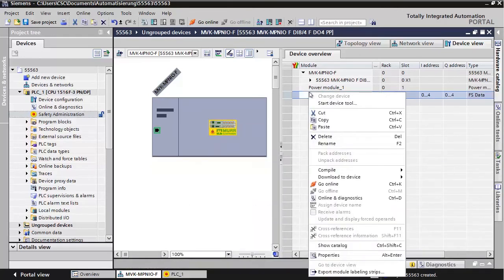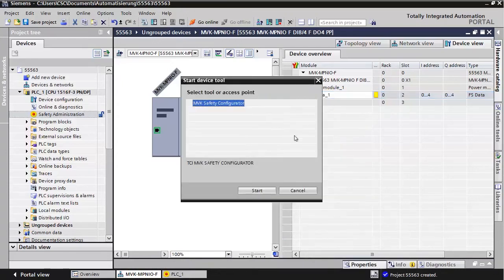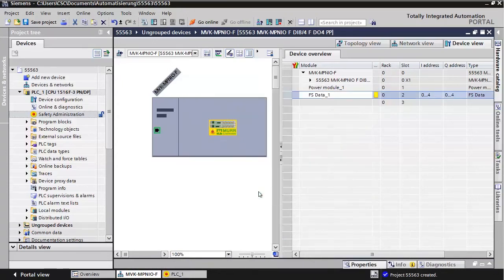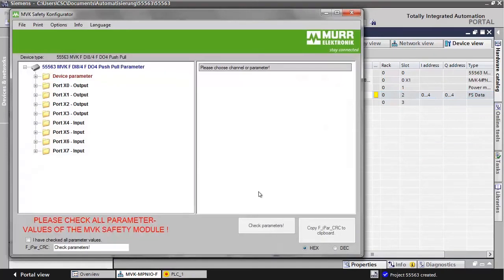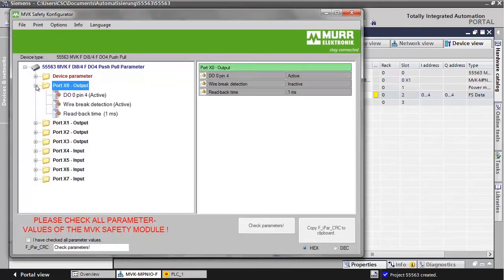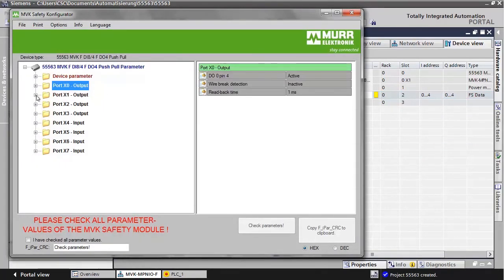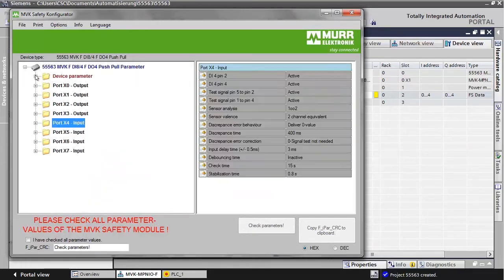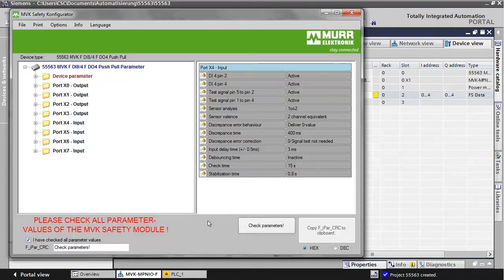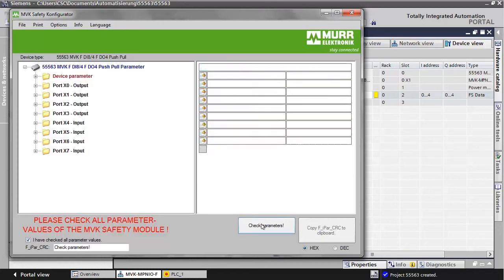Right-click on the FS Data and select Start Device Tool. Check all parameter values of the MVK safety module that were previously defined. After that, confirm that they are correct by checking the box, I have checked all parameter values. Click on the button Check parameters.